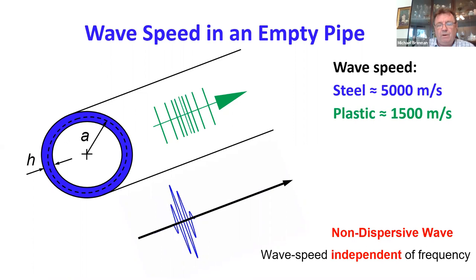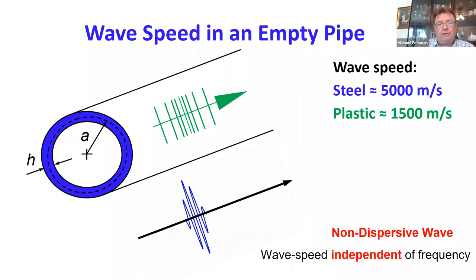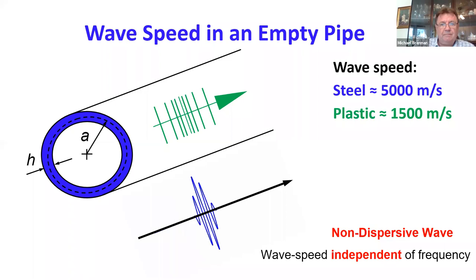This is a wave where the wave speed is independent of frequency, which means it is non-dispersive. What non-dispersive means is that if you inject a waveform into the pipe wall, it will propagate without distortion. It is particularly fortunate for leak noise propagation that the waves we are interested in are non-dispersive — that the wave speed is independent of frequency.